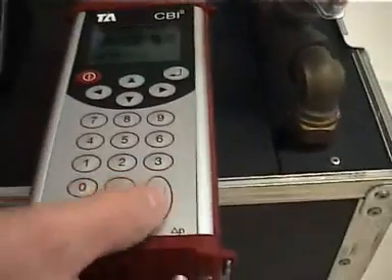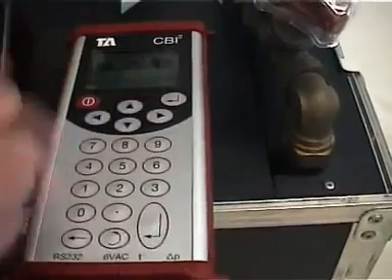We have a differential pressure across the top two valves at 17.78 kPa. We want to check to make sure that we have a correct flow rate coming through from the system. We press our enter key because the machine tells us we want to measure the flow.